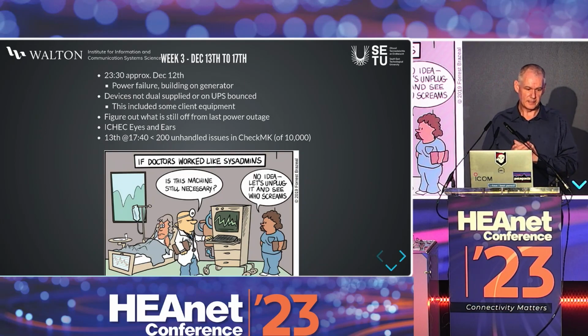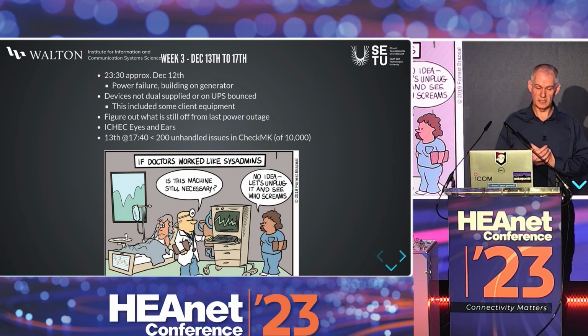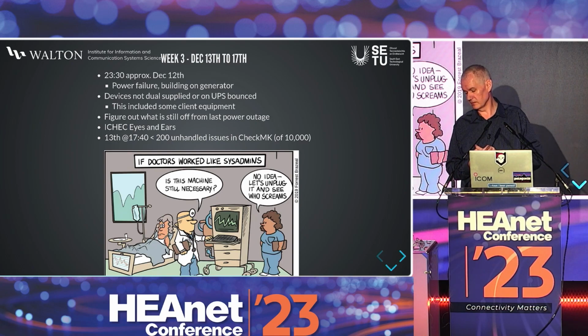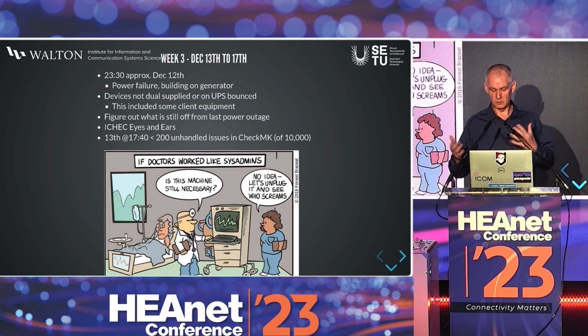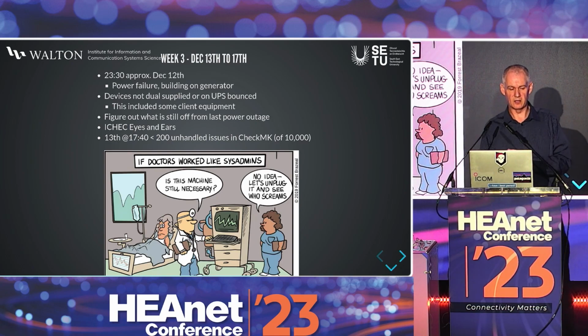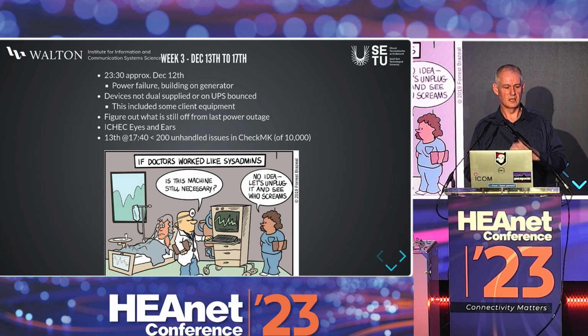So then, week 3, Sunday night about 11:30, there was a power failure on the site. We're on a spur, ESB spur, so we do get power failures for various reasons. Building went onto generator, but not everything — we hadn't twigged every device or caught every device that wasn't dual supplied, so some stuff dropped, including some client equipment.